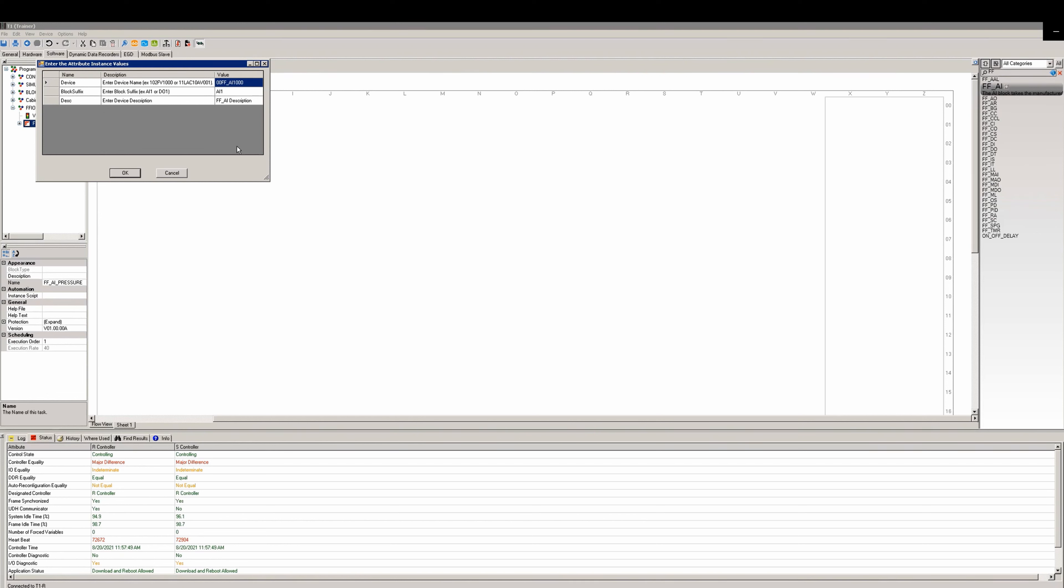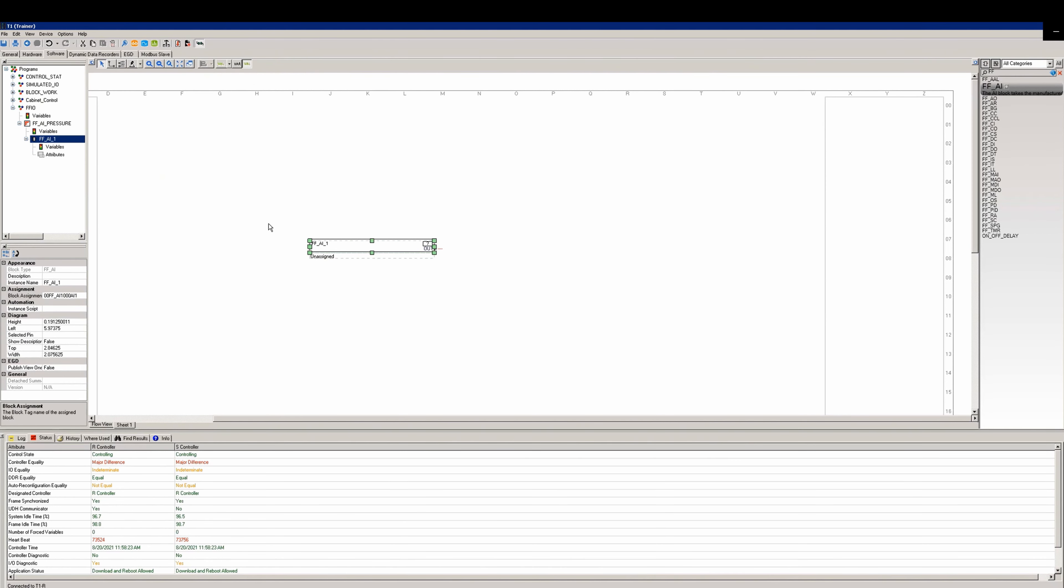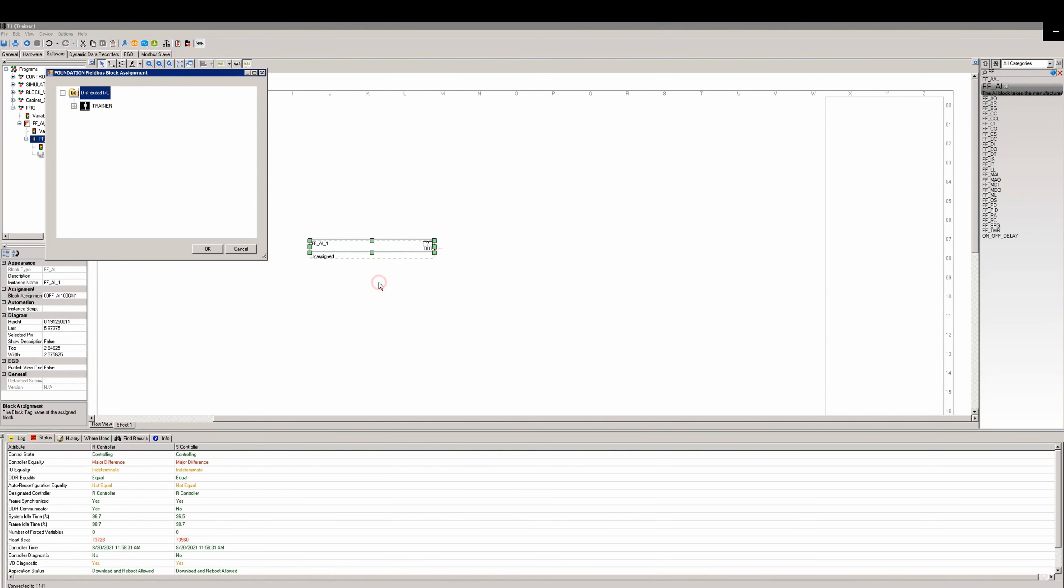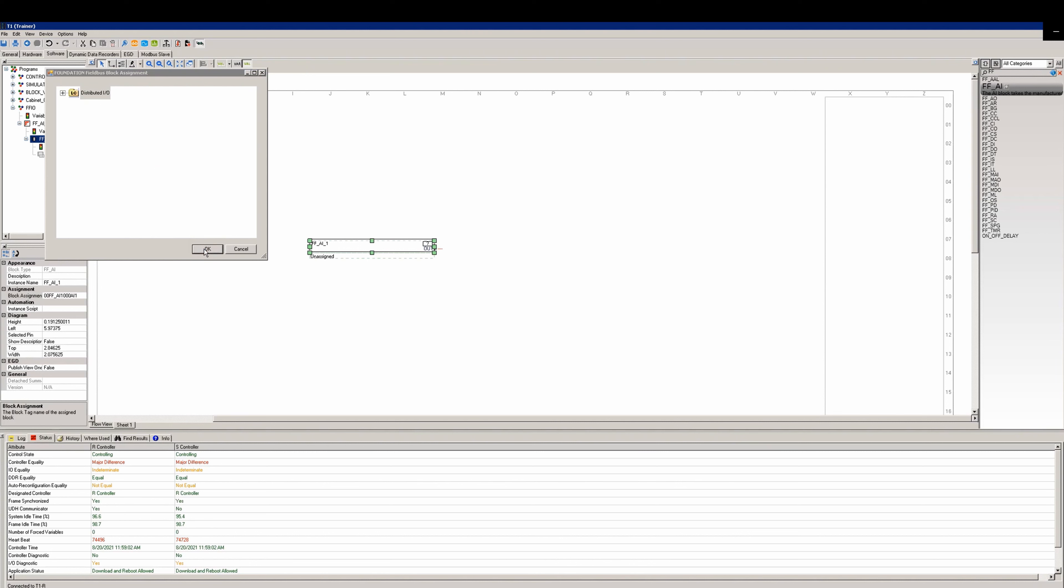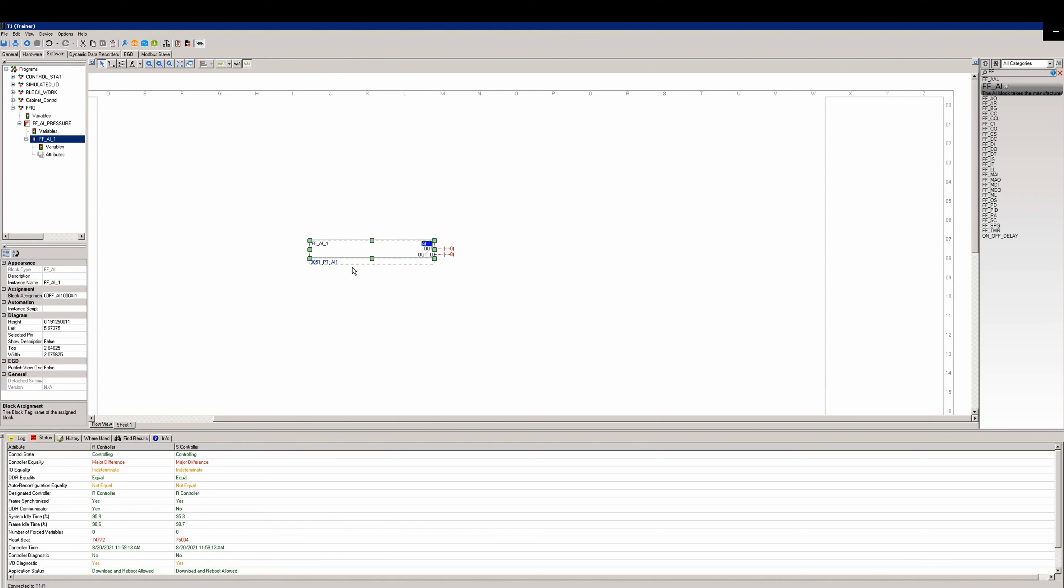Select the arrow tool and then add an FFAI block. We'll then fill out the device name, the device suffix, and the description and click OK. The block will show that it is unassigned. Right-click on the block and select assign. Then from the pop-up select the device placeholder AI input 1 and click OK. If done properly, the unassigned will change to the AI block name, in this case 3051_PT_AI1.